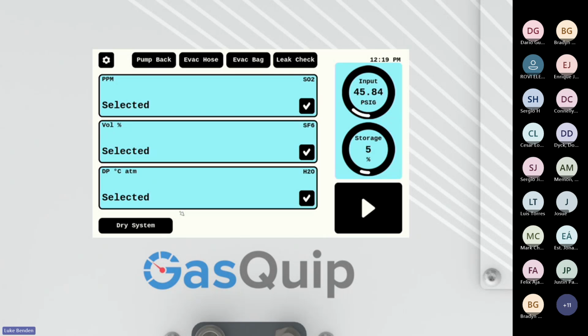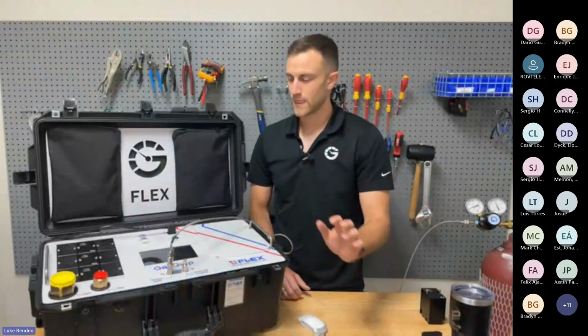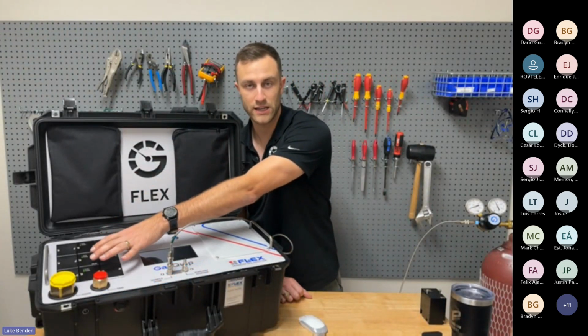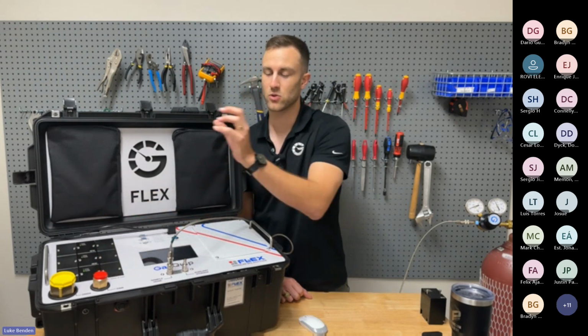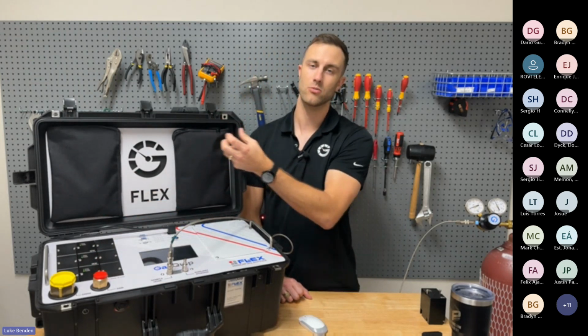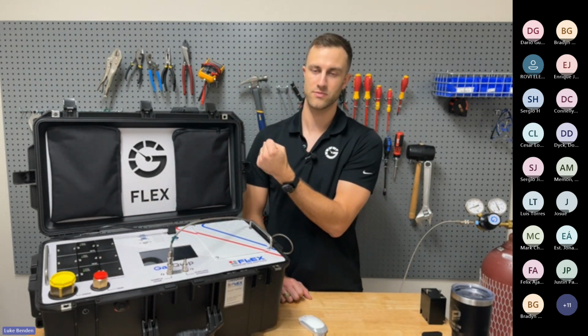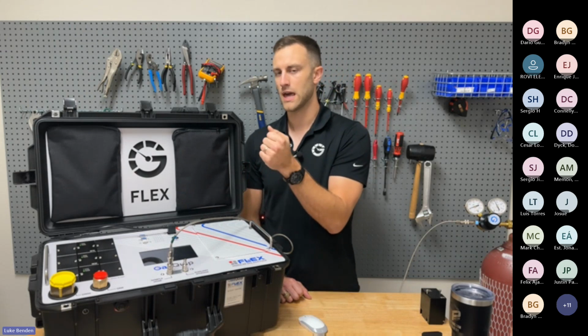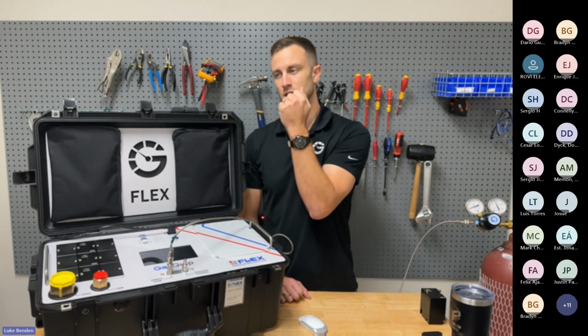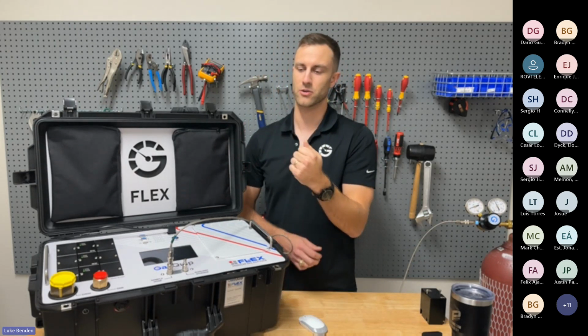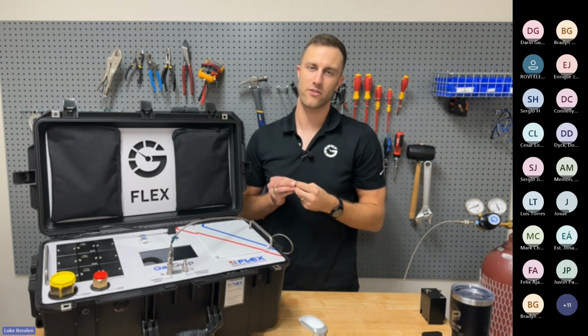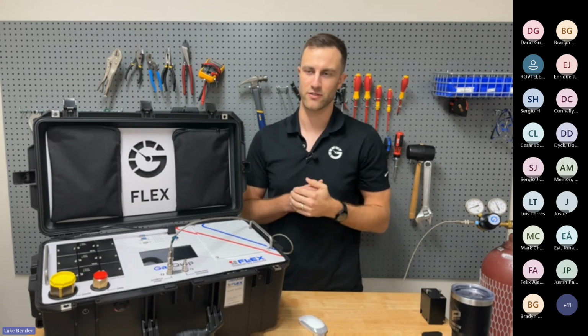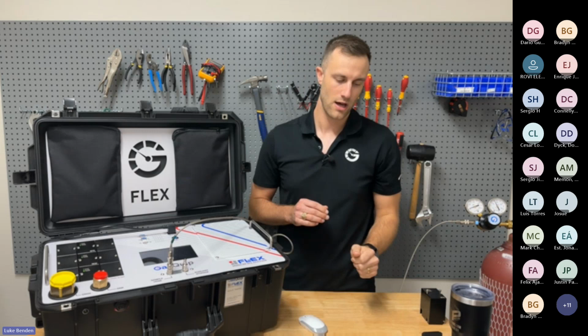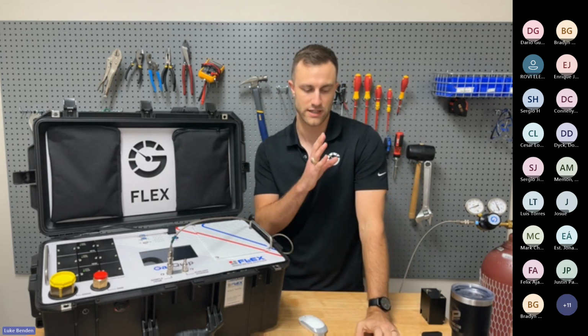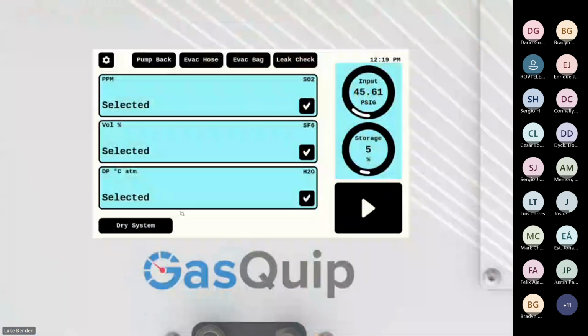So what happens is, go back to here. The H2O sensor will run that heater for 5 minutes, and then the vacuum pump will also pull a vacuum on all of the internal sensors, modules, plumbing, and that helps to start from a clean slate, like we talked about earlier, pulling all that moisture out of the device that might have seeped in, or if it's just been stored or whatever. It's a good way to start from a clean slate and dry everything out. So that's all of those functions.